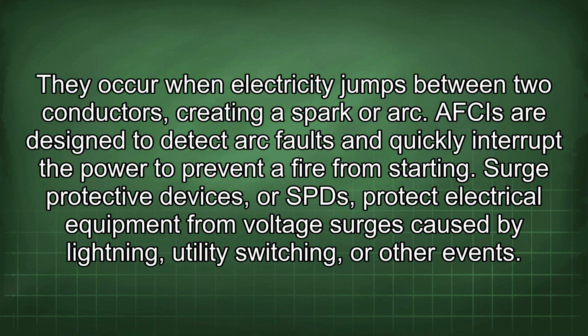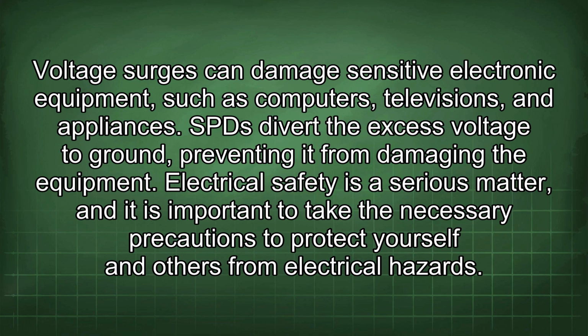Surge protective devices, or SPDs, protect electrical equipment from voltage surges caused by lightning, utility switching, or other events. Voltage surges can damage sensitive electronic equipment such as computers, televisions, and appliances. SPDs divert the excess voltage to ground, preventing it from damaging the equipment.